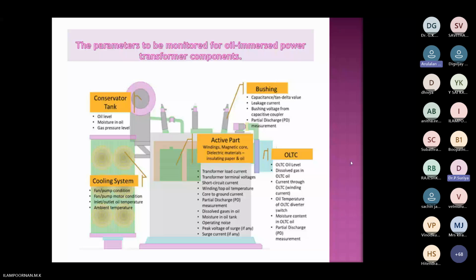I think it provides supporting insulation also. Insulation between the internal and external connections. Yeah, perfectly. It is for insulation between the winding and the tank. If you bring a simple wire, it will just short circuit and the tank will get energized. So you need a bushing for the exit of high voltage from the winding directly to the line, bypassing the tank. The tank should be insulated from the actual conductor. So that is why the bushing is there.